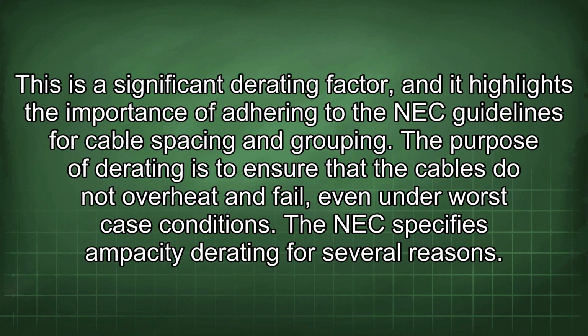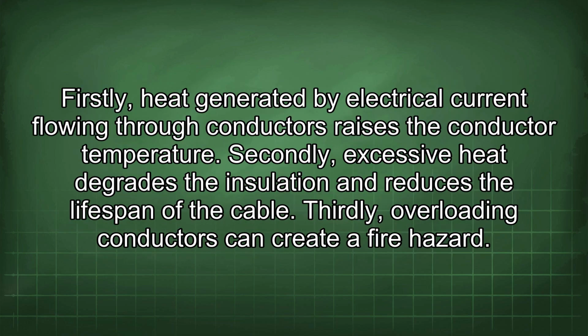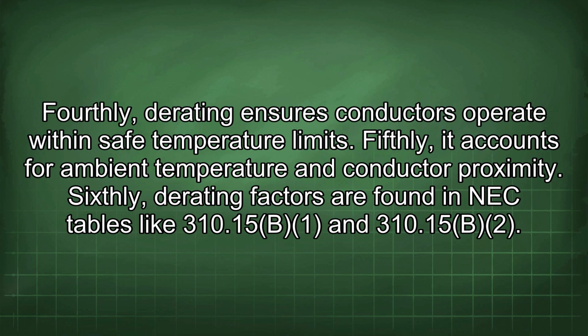This is a significant derating factor, and it highlights the importance of adhering to the NEC guidelines for cable spacing and grouping. The purpose of derating is to ensure that the cables do not overheat and fail, even under worst-case conditions. The NEC specifies ampacity derating for several reasons. Firstly, heat generated by electrical current flowing through conductors raises the conductor temperature. Secondly, excessive heat degrades the insulation and reduces the lifespan of the cable. Thirdly, overloading conductors can create a fire hazard. Fourthly, derating ensures conductors operate within safe temperature limits. Fifthly, it accounts for ambient temperature and conductor proximity.